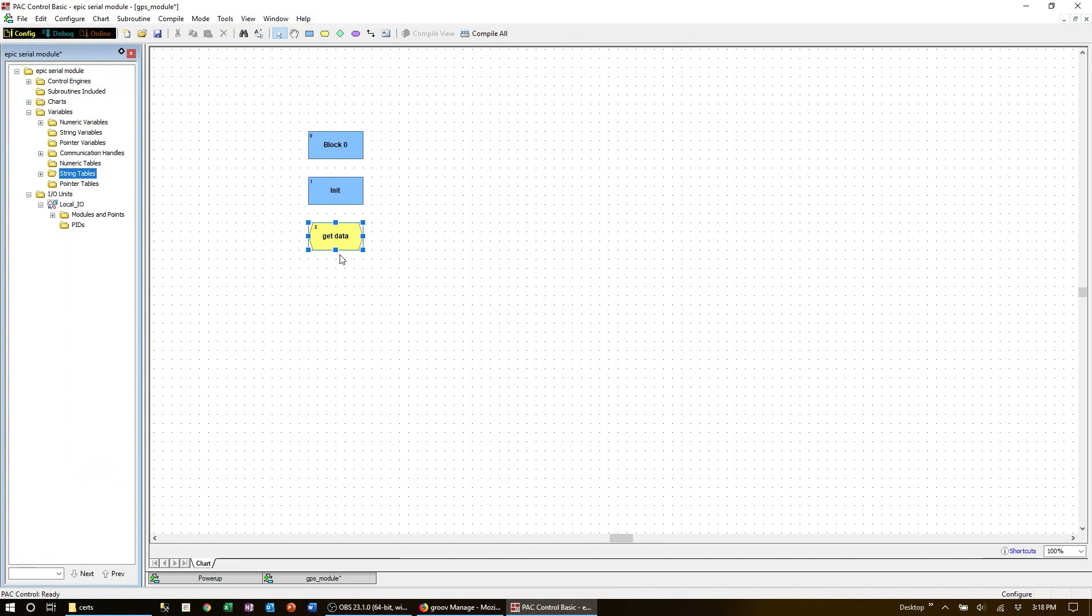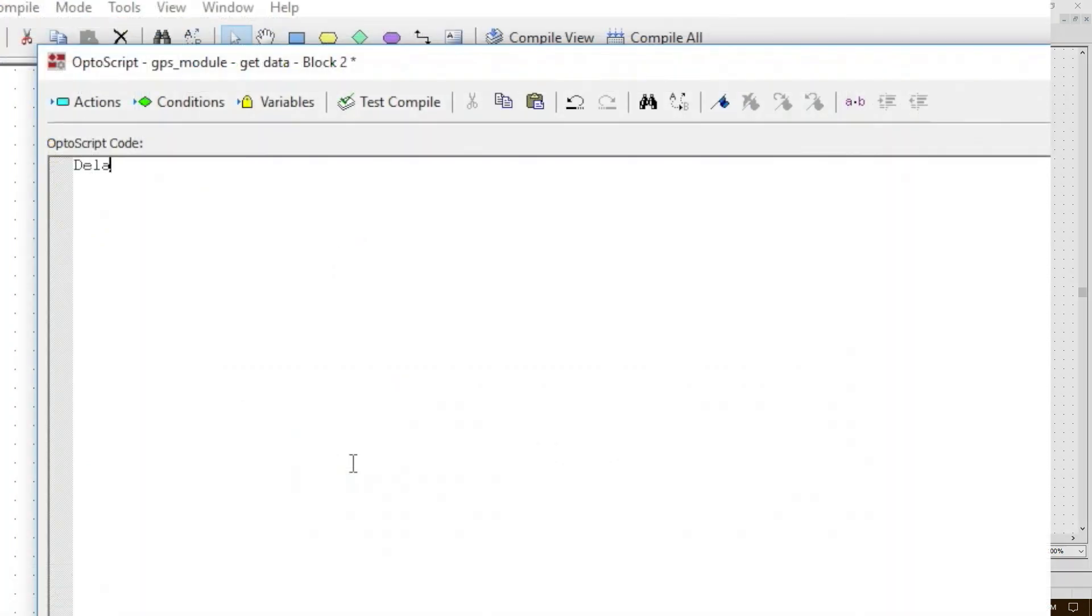Since we're going to loop around here waiting up to a second for the data to arrive, we need to add a delay. Every chart must have a delay in any loops—this is not optional. So we're going to add a small delay here, say 10 milliseconds.